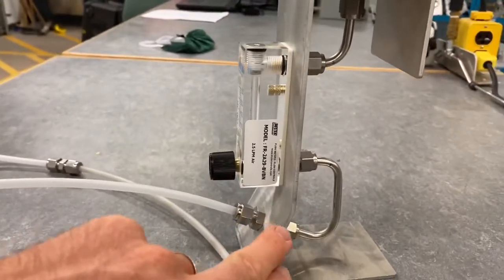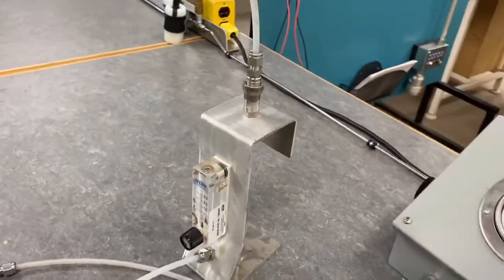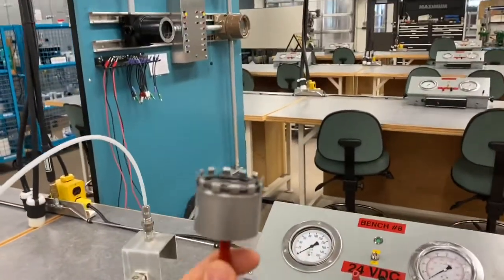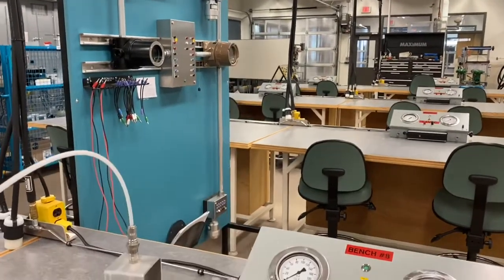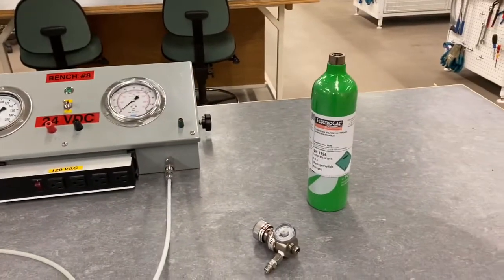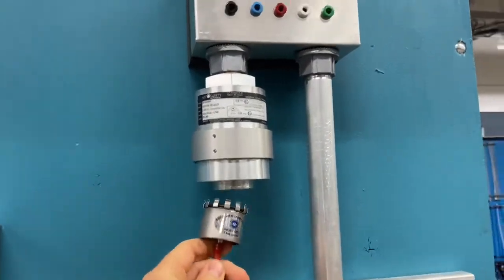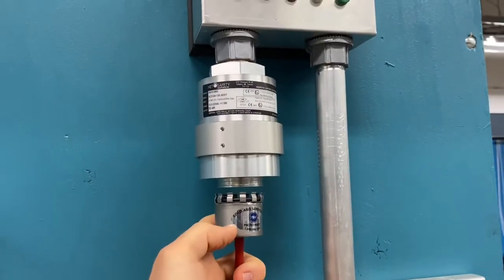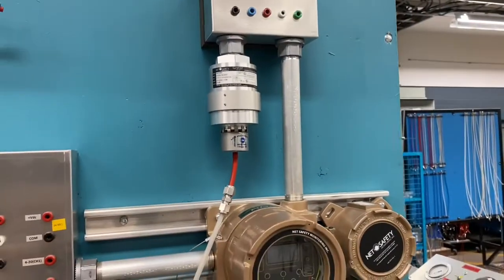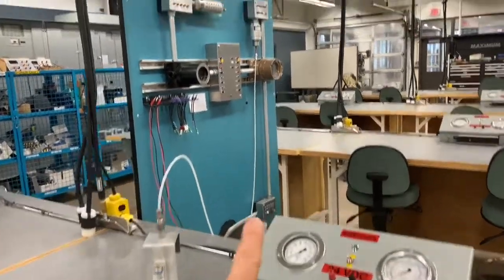The air comes in the backside and goes up to the bottom and through the top and exits. We've got our quick connect fitting here, exits out the top and comes down and around to our calibration cup. This calibration cup fits onto either the top sensor or the bottom sensor and allows us to expose them to either the zero air or the H2S. I'll show you how the calibration cup fits onto the top sensor. There's an O-ring in here to help prevent the gas from leaking out around the sensor. It just clips on there. I'll take you around and get some instrument air flowing. You can see it's run out through the variable area meter and over to our top sensor.